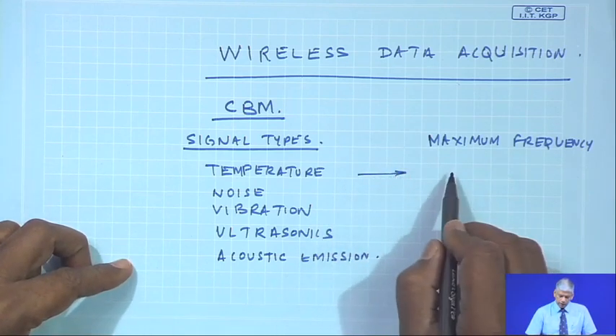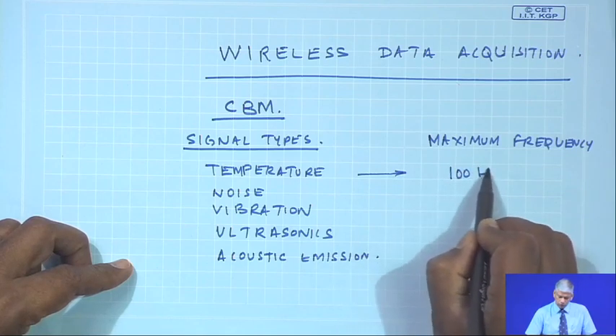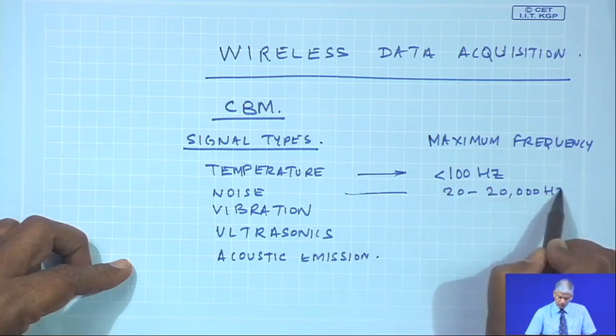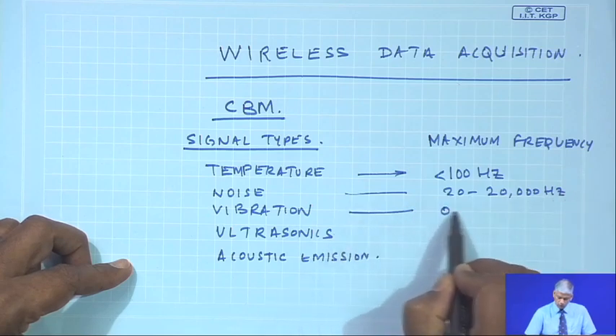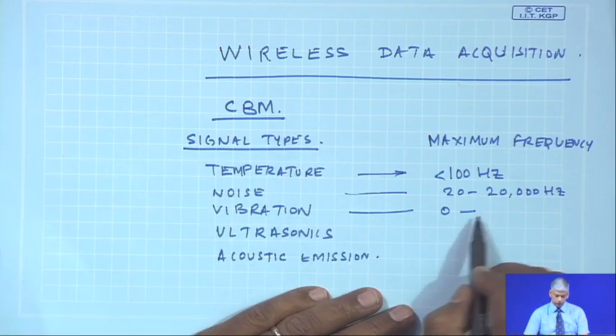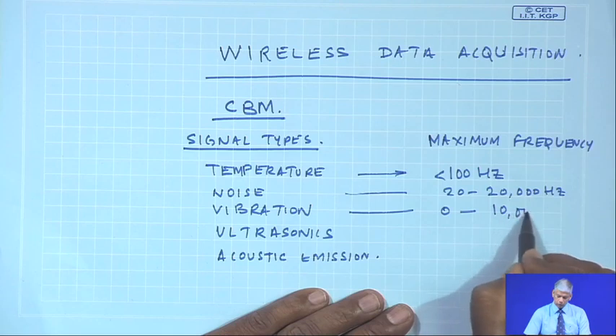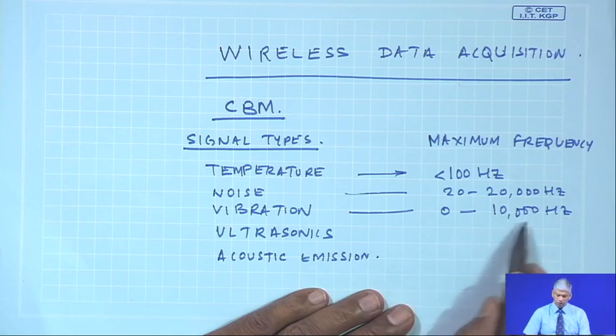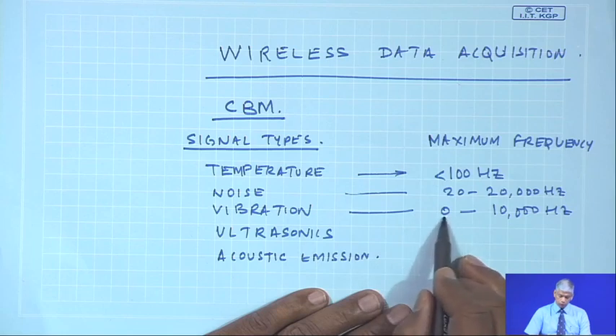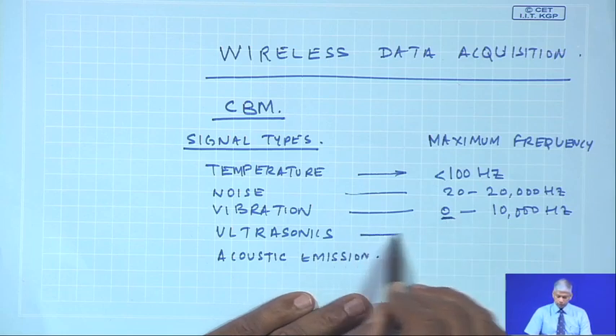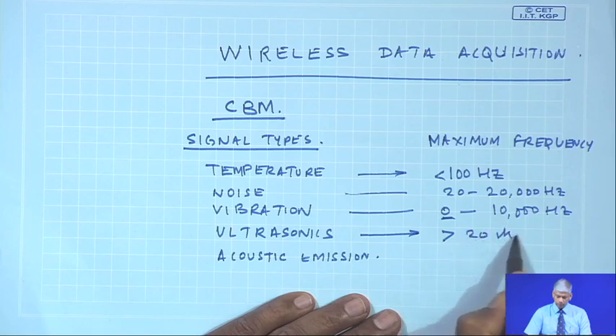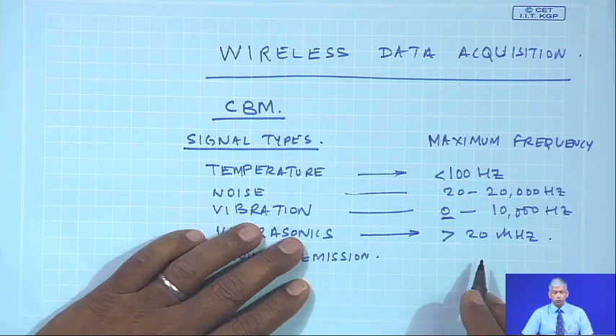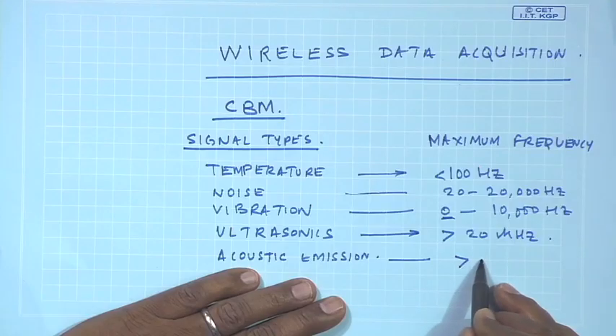Typically in mechanical systems: temperature frequency is less than 100 Hz; noise is 20 to 20,000 Hz; vibration is anywhere from 0 up to about 10,000 Hz — because sources of vibration like electrical motors, IC engines, and machineries have enough information up to about 10,000 Hz. Ultrasonics is anything greater than 20 kHz — used for NDT and sonars for navigation — and acoustic emission could be greater than 1 MHz.